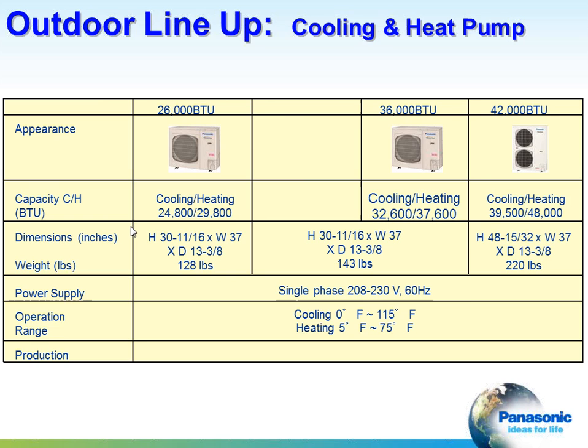Here's a lineup of the outdoor units. And again, they come in a range of 26,000 BTUs to 42,000 BTUs, both in cooling only and in heat pump. Dimensions are there, fairly small equipment, easy to handle by 1 or 2 people. And again, power supply is 230 single phase. Range of operation is down to 0 degrees in cooling and down to 5 degrees in heating. This becomes important. Typically speaking, you're not going to rely on this equipment as a sole source of heating. We do have auxiliary means of controlling auxiliary heat with this equipment as well.